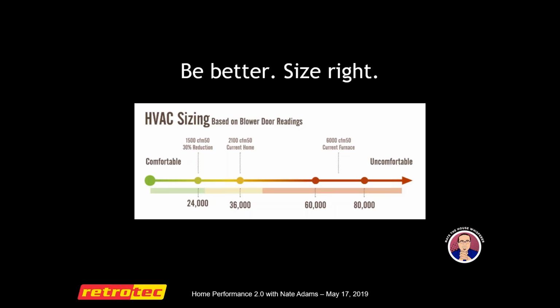So here you are. If you don't know what the blower door result on that house is, and these three numbers, by the way, 1,500 to 6,000, we've seen these on houses when we've tested them, so if you don't test, you have no clue what the right piece of equipment is, and you're going to lean towards the bigger side. I understand that, that's being safe and cautious. But if you do a blower door test, your sizing gets much less scary. Rather than choosing between 5 or 6 different sizes of equipment, you'll narrow it down to 1 or 2. So if you want to be better, sizing right is really critical.